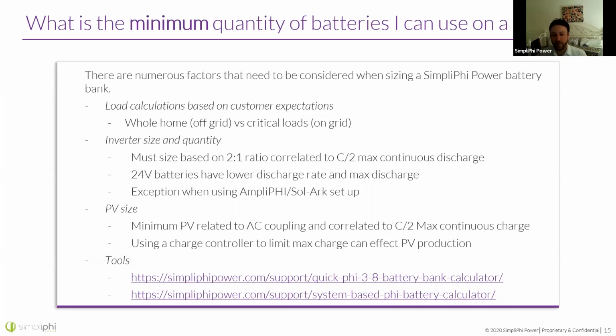So if you have 3 batteries, it is 1.9 times 3, not just 1.9 for the entire thing. But again, 2-to-1 ratio being the easiest way to solve this. Let's take it kind of backwards: if you have 8 kilowatts of inverting power, the minimum quantity of batteries is just double that. It's 16 kilowatt hours of batteries minimum.